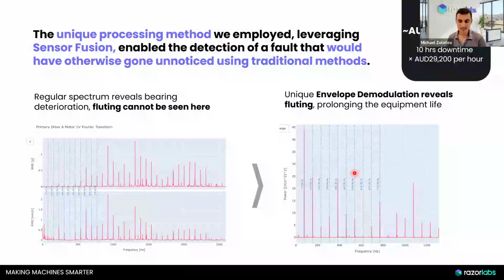You can already see the difference between this system and other systems. We do not look at vibration alone. We've seen cameras, we've seen motor current and tachometer all put together, just in this case of the conveyors, but also the ability to not transfer the workload of identifying what should be the threshold of every frequency to the site, which many systems do. This system comes already pre-equipped with the knowledge of what needs to be looked at and what is the right way to perform diagnosis. And especially, it's basically a recommendation system to the site experts.